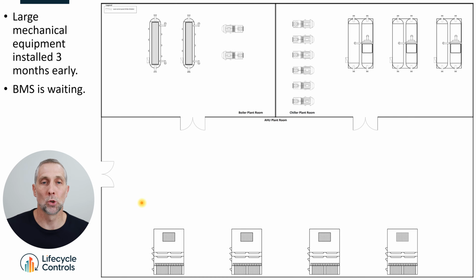Now what happens is usually very large mechanical equipment is installed very early in projects. You can't carry a chiller down a flight of stairs into the basement. So usually before the slab for the plant room goes on, they would install this big equipment in there, or maybe this wall over here wouldn't be here, and they'd slot these boilers in here and then build the wall afterwards. But either way, large mechanical equipment is sitting in plant rooms for 2 or 3 months and nothing's happening to them.